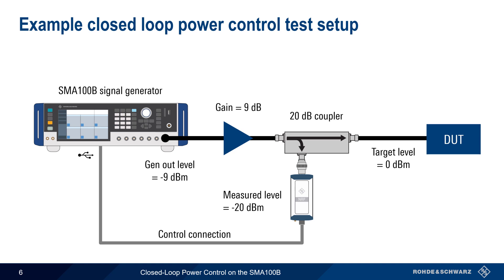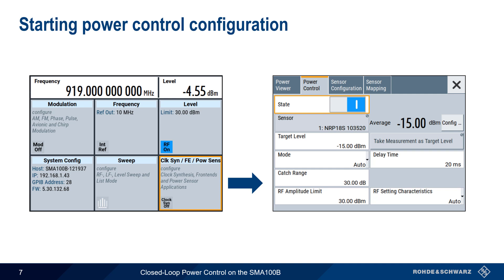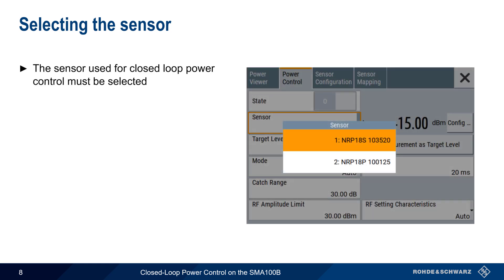In the remainder of this presentation, we'll show step-by-step how to configure closed-loop power control using the SMA100B and an NRP series power sensor. On the SMA100B, power control is configured by first clicking on the Clock Synthesis FE Power Sensor tile in the main GUI. Power control is then configured by clicking on the Power Control tab. Note that power control is configured entirely through the SMA's GUI — no external software or control PC is required.